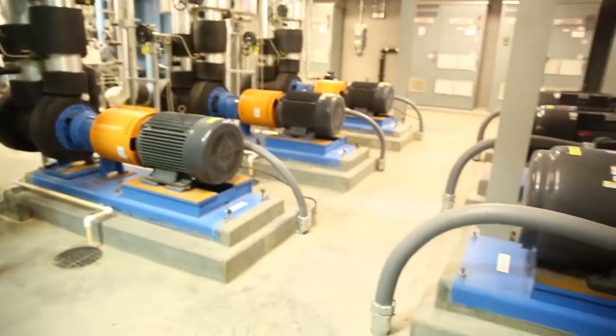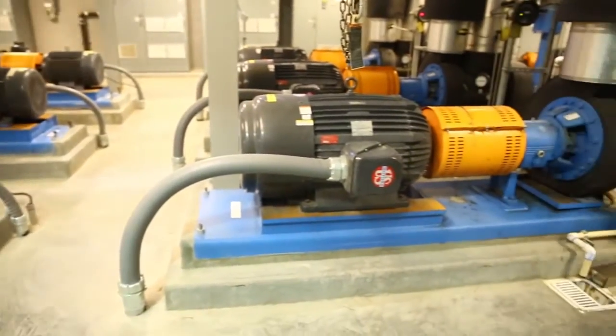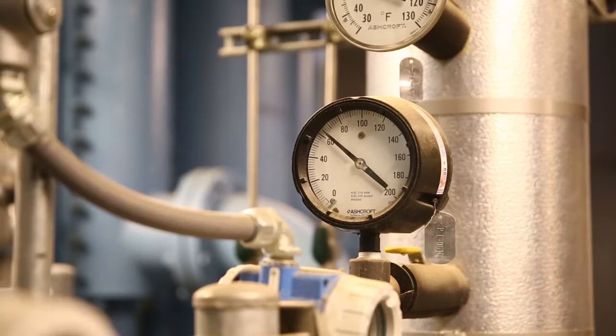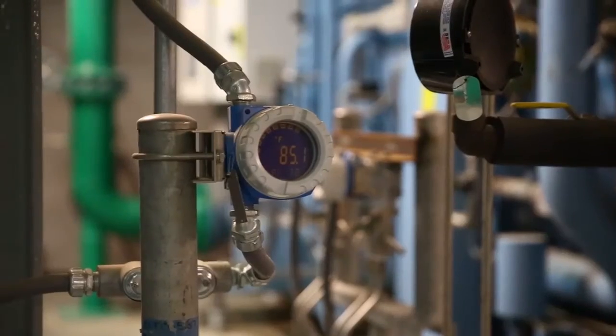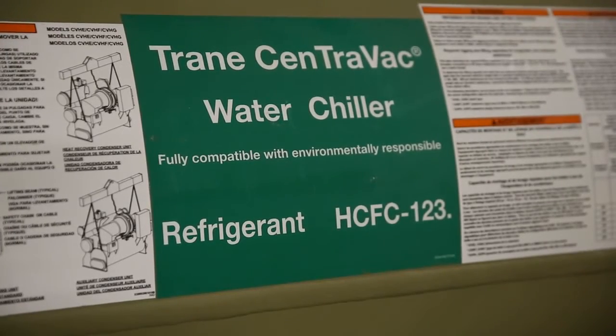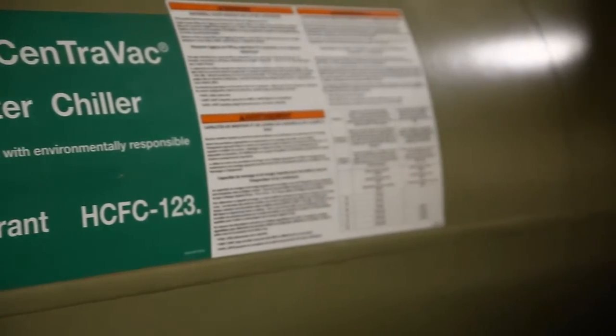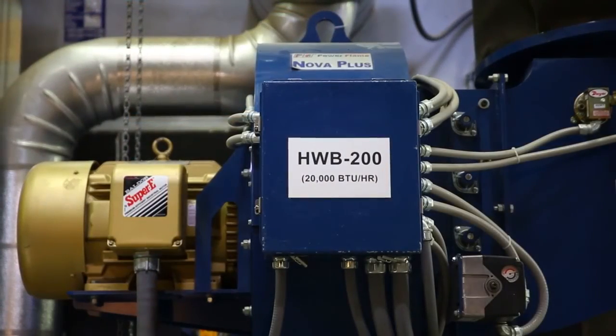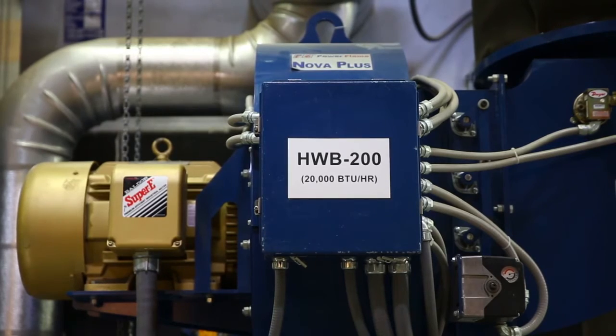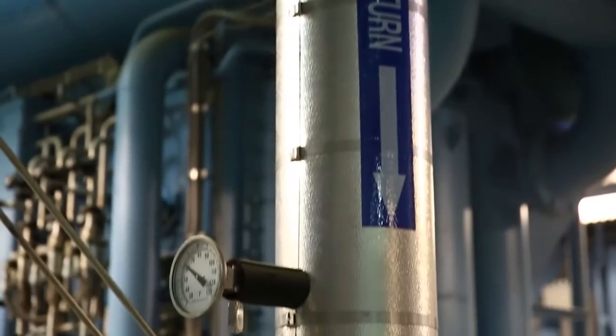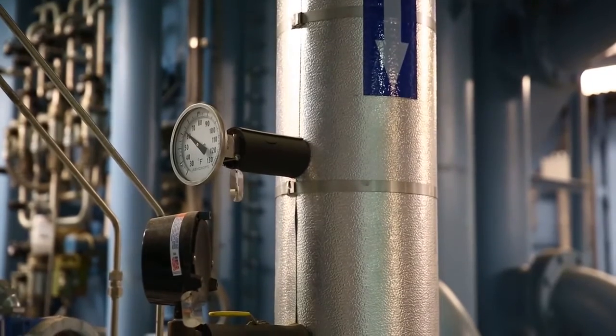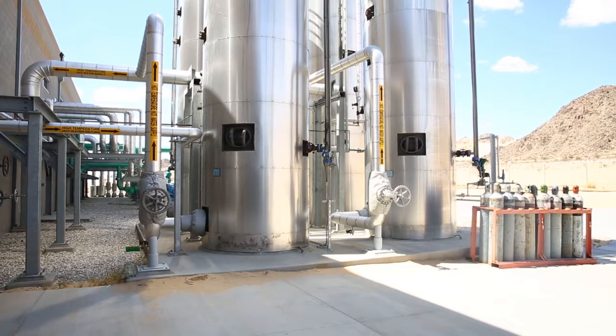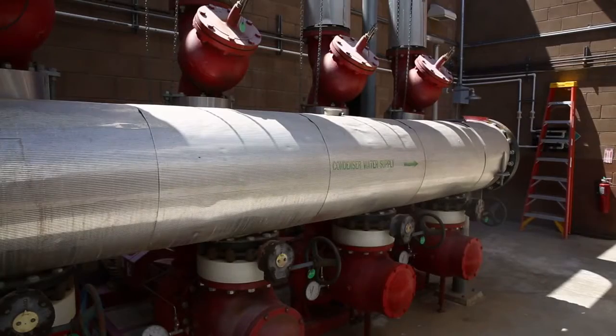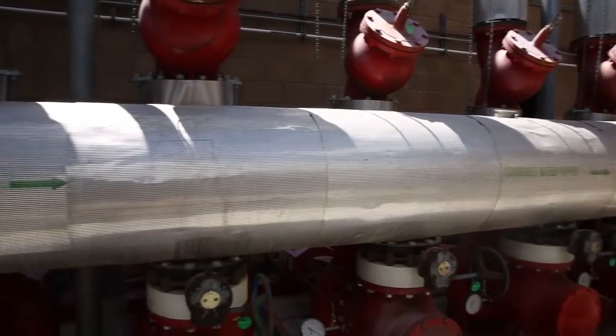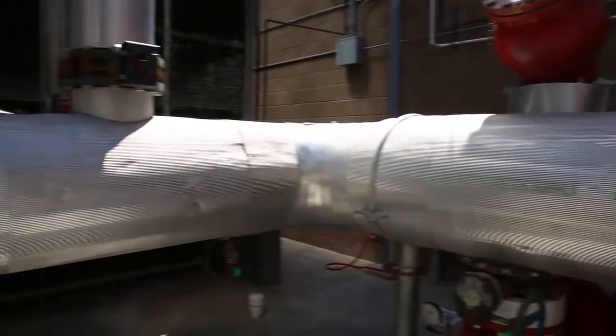Our systems on base are very efficient. They utilize central chilled water plants and central heat plants, which use all the waste heat from our generation. The chilled water plants are basically large AC units on a plant-size scale, providing cooling to multiple facilities, supplying about 60% of buildings on base with chilled water. The high temperature hot water of the cogen plant supplies about 80% of buildings on base with heat, domestic hot water, and steam.